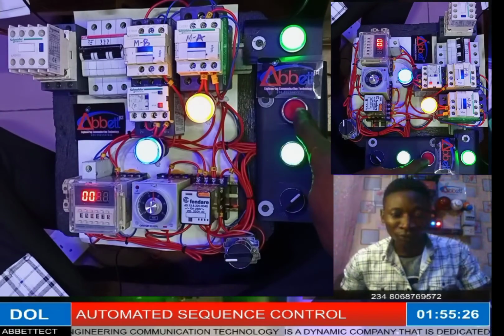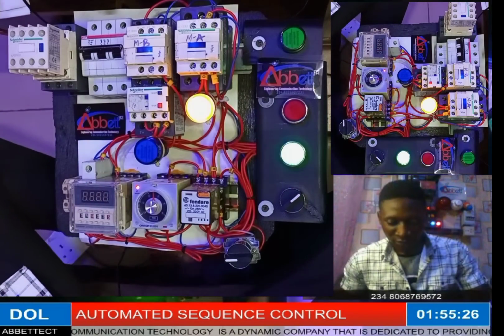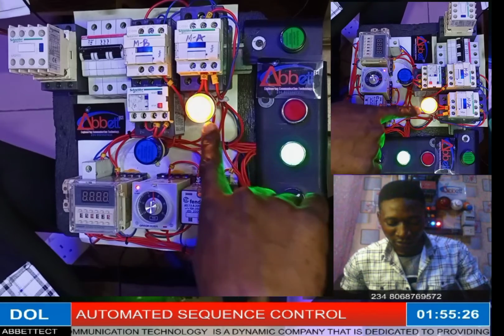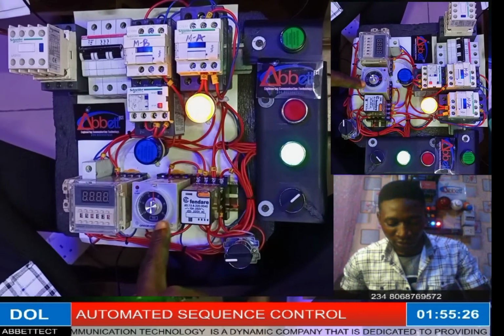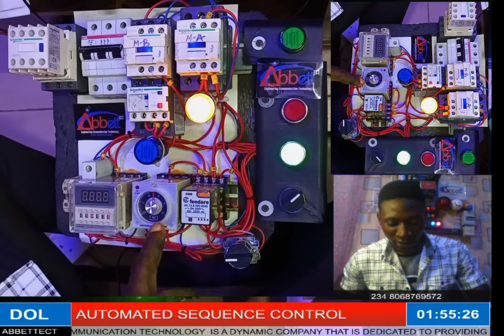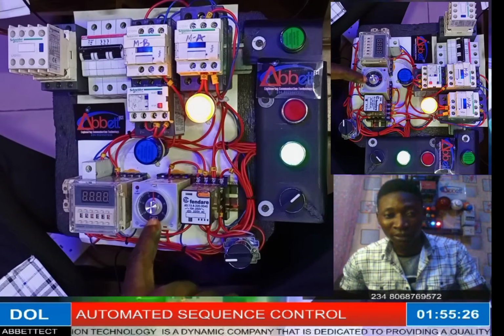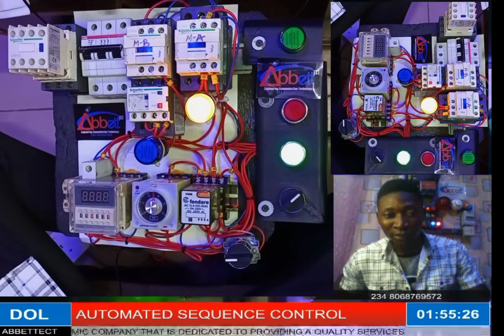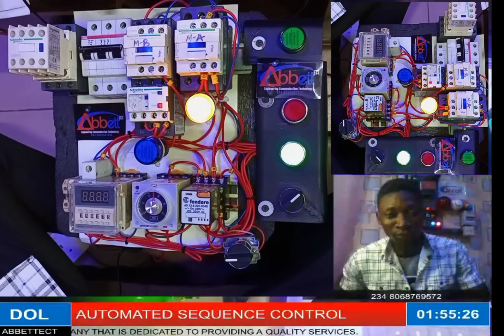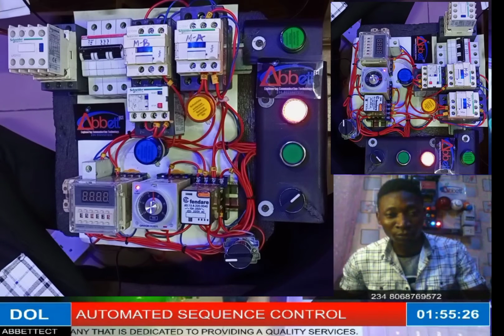So let's stop now. You will see the delay time will be longer. You see now? I've stopped the system, but motor A is still on based on the stopper timer that is attached to it. So this one will dictate to this one when to finally stop. You see now, the system is working perfectly.